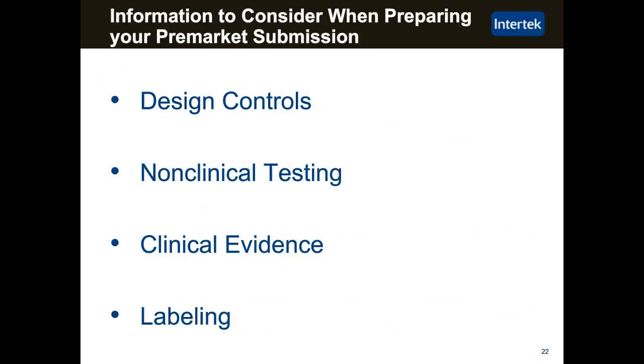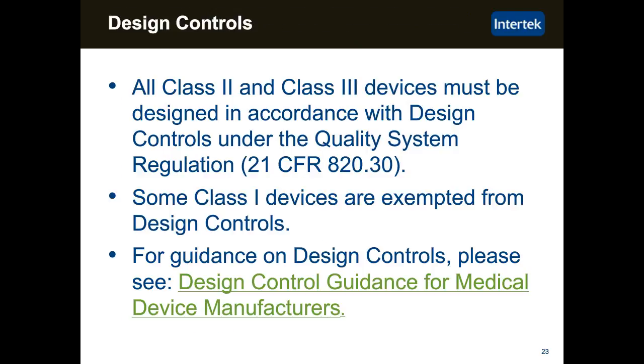Typically, the information you're going to need to consider when preparing your pre-market submission includes design controls, non-clinical or preclinical testing, your clinical evidence, and the labeling that will accompany the device. Let's talk a few seconds about design controls.